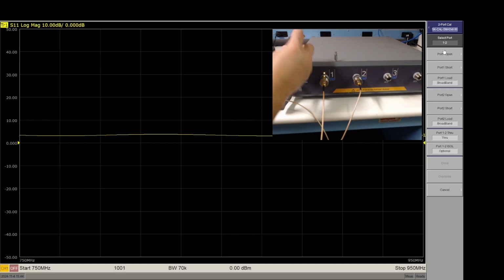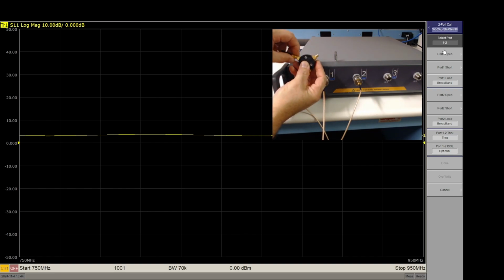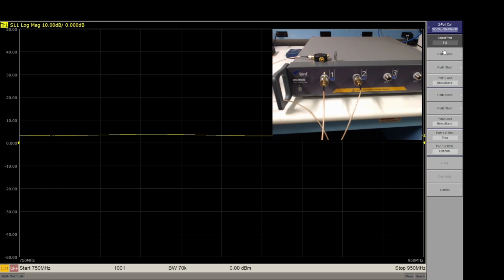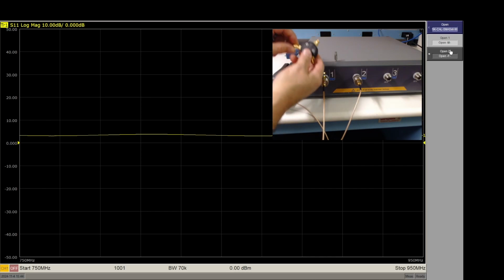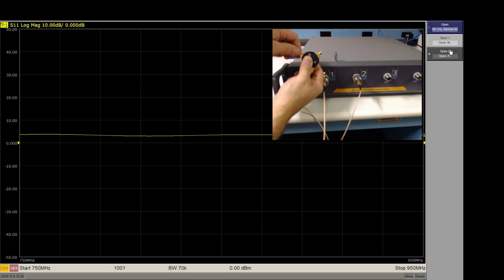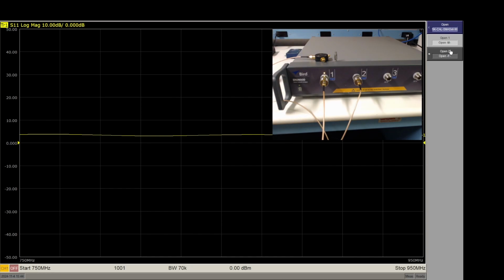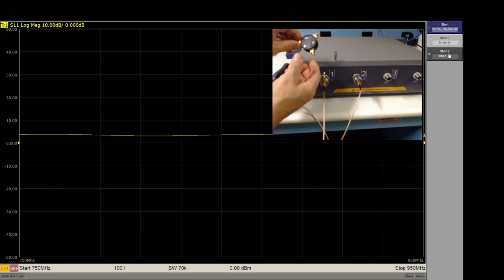Connect the part of the standard marked with an O for Open to the end of the cable leading from port 1. Click on the port 1 Open button in the software interface, then click the Open F since the connector type on the standard is female. Next, connect the part of the standard marked with an S for short to the end of the cable. Use the function buttons to navigate up a level and click on the port 1 short button in the software interface. Then click the short F.